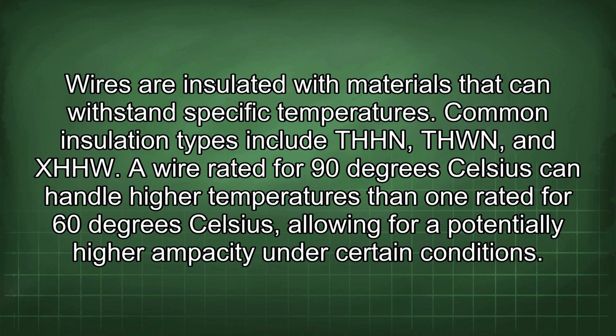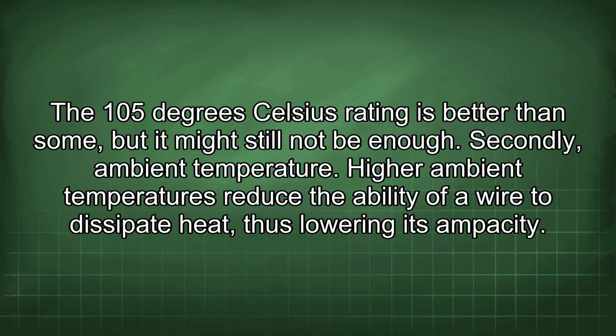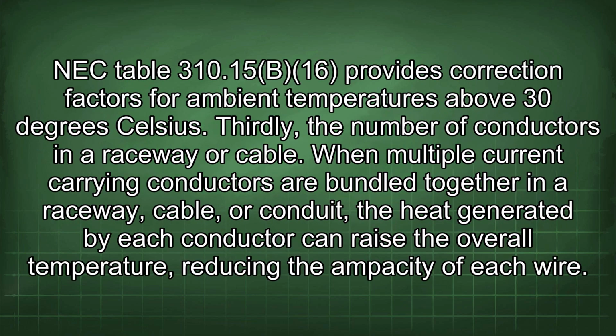A wire rated for 90 degrees Celsius can handle higher temperatures than one rated for 60 degrees Celsius, allowing for a potentially higher ampacity under certain conditions. The 105 degrees Celsius rating is better than some, but it might still not be enough. Secondly, ambient temperature. Higher ambient temperatures reduce the ability of a wire to dissipate heat, thus lowering its ampacity. NEC Table 310.15(B)(16) provides correction factors for ambient temperatures above 30 degrees Celsius.